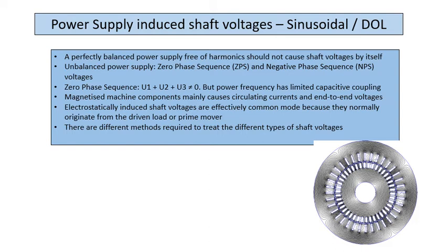Your unbalanced power supply, so you've got zero phase sequence and negative phase sequence components. The negative phase sequence just causes a field to rotate in the other direction, so it should have a pretty similar effect to positive phase sequence, just that the frequency will be higher.